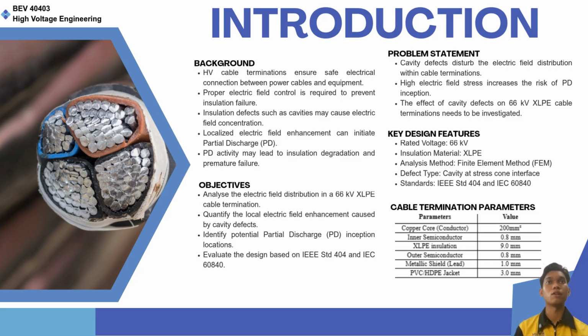We move to the objective. The study aims to analyze the electric field distribution of a 66 kV XLPE cable termination, quantify the field enhancement caused by cavity defects, identify potential PD inception location, and evaluate the design based on the IEEE Std 404 and IEC 60840.